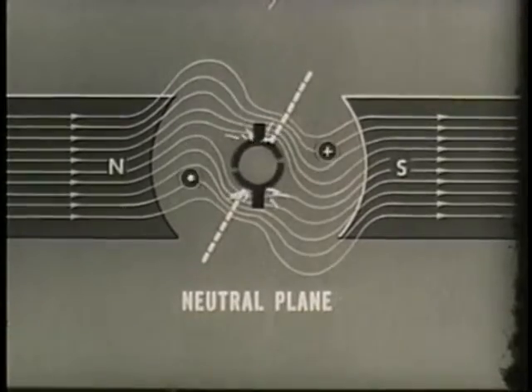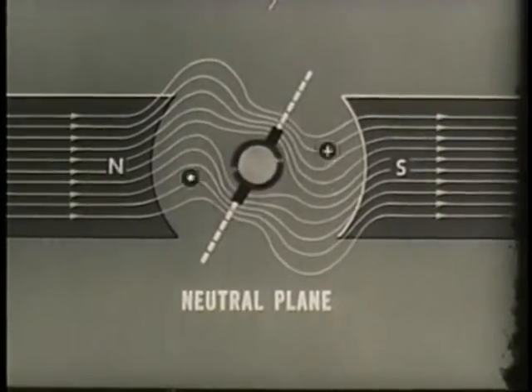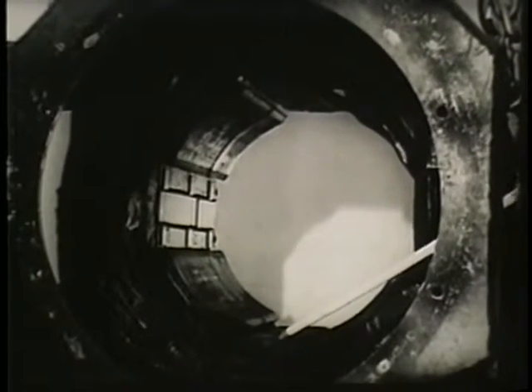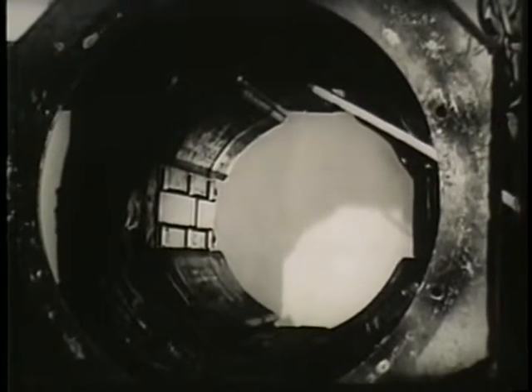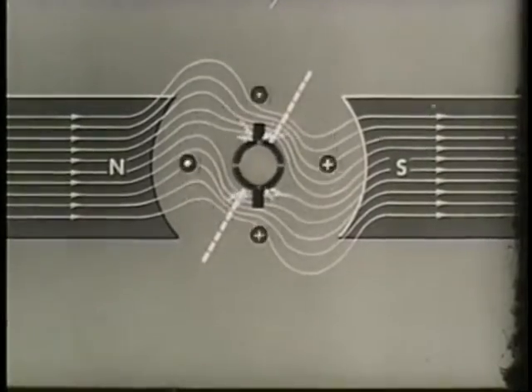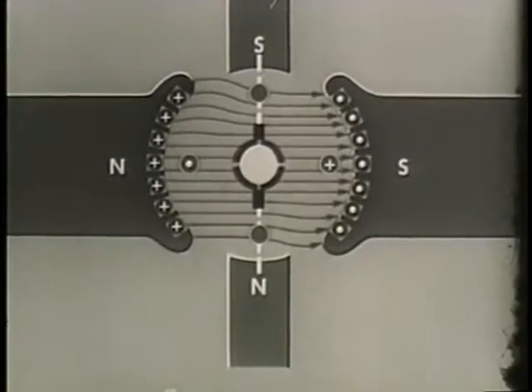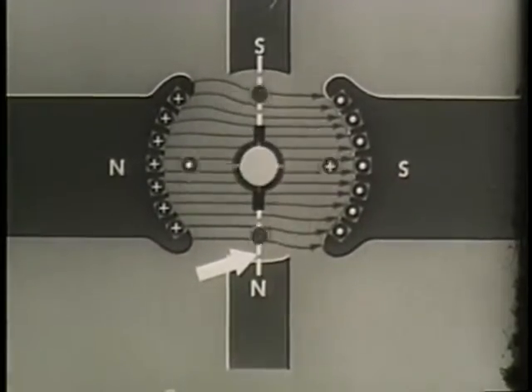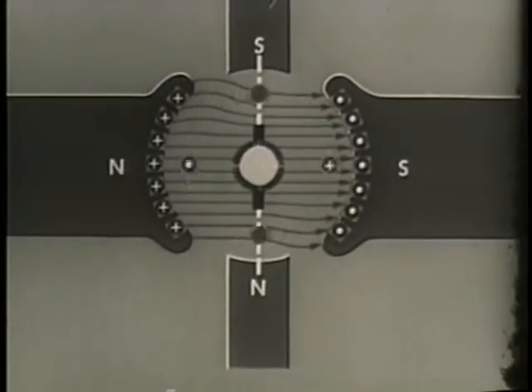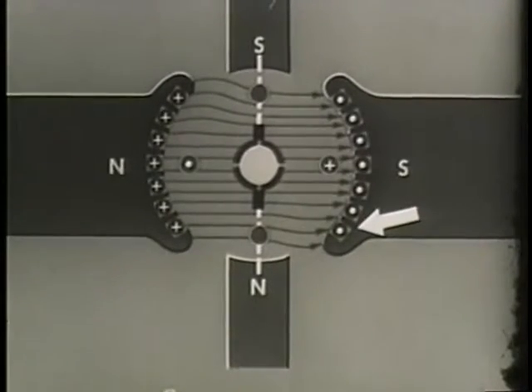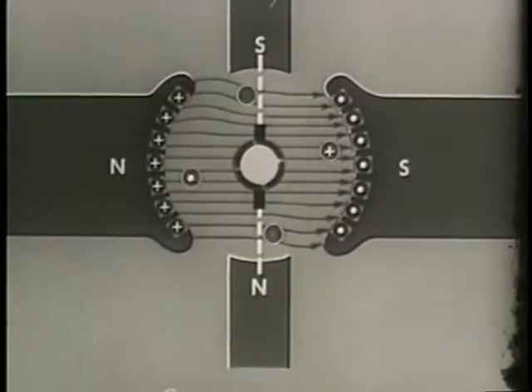There are two ways of maintaining the neutral plane in its correct position and thus avoiding sparking. It may be done by the adjustment of the brush position — the brushes are adjusted to lie in the adjusted neutral plane. The other way is by adding interpoles to the generator field. These interpoles are small magnets placed between the poles of the main field magnets. The interpole fields oppose the fields created by armature reaction. In addition, to further counteract armature reaction, windings called compensating windings are sometimes placed in the main pole faces. The current in these windings is armature current flowing in the opposite direction to the current in the armature conductors.